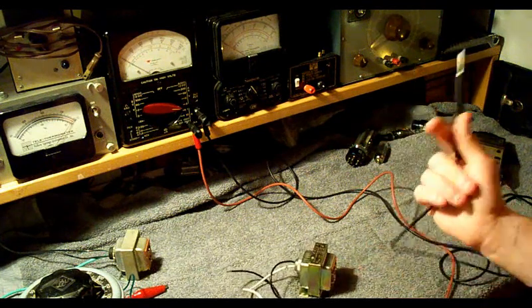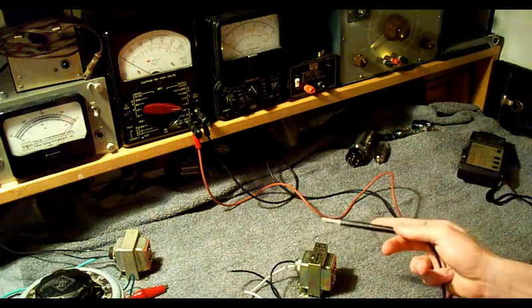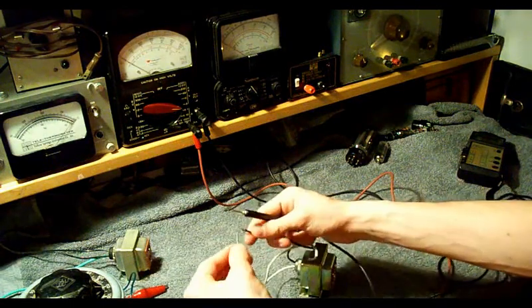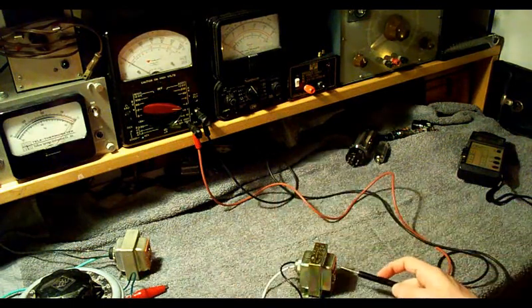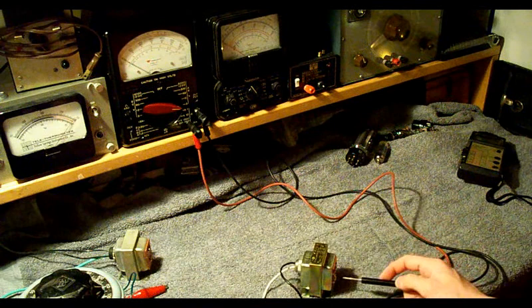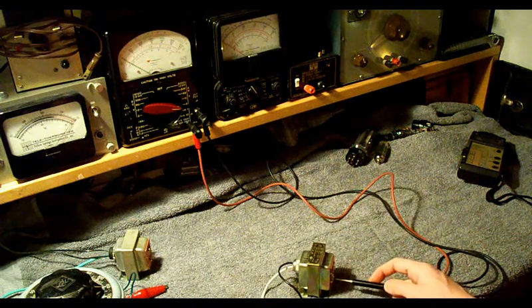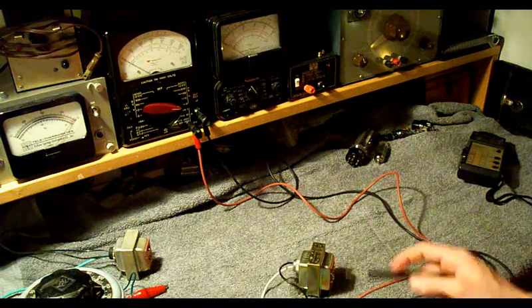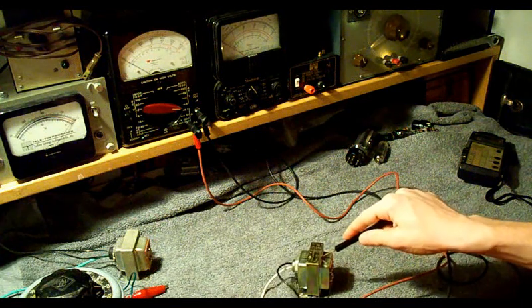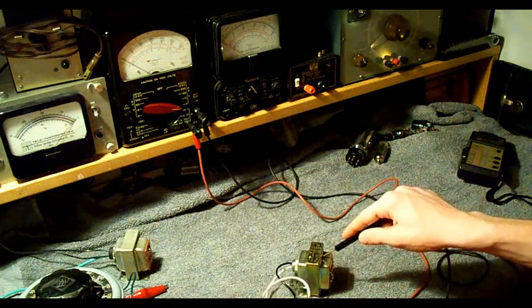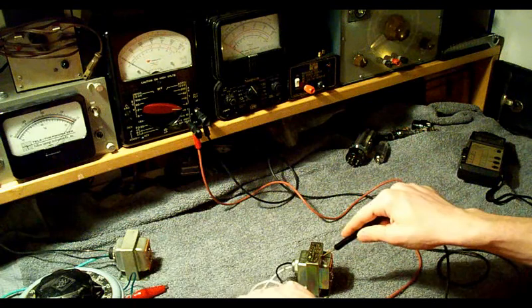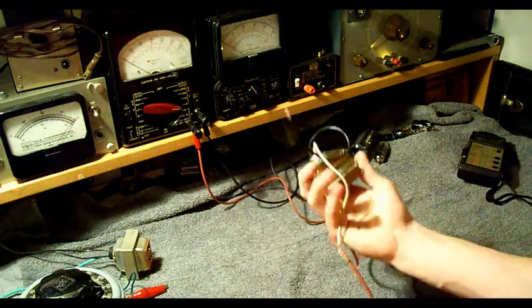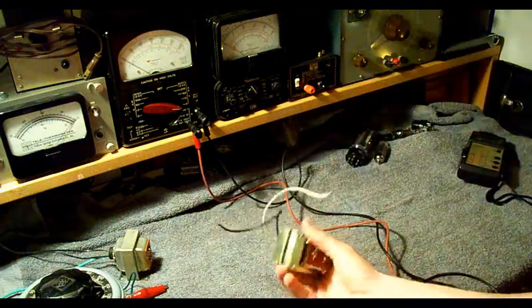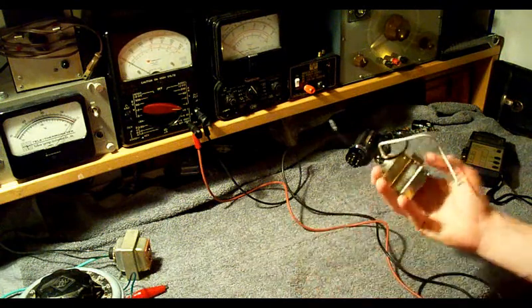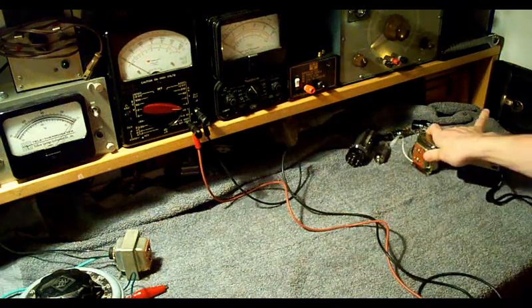No continuity. If we get continuity here, the transformer has an internal short and is defective. Now we'll go the other side of the primary to one side of the secondary and the other side of the secondary. Nothing. And now finally we'll check the primary to the case. Nothing, and let's see, nothing. So this transformer tests good. There are no shorts in the transformer and both windings read intact. And we'll show you this later.